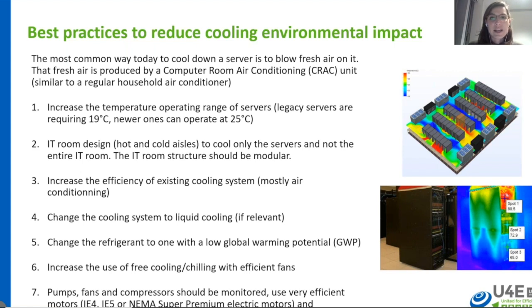For instance, increase the temperature operating range of the server. The second is IT design to cool only the server and not the entire IT room, so the IT room structure should be modular. Data center operations change over time, new servers might be added due to business growth, so it's important the data center can adapt to these changes and save energy on cooling by incorporating modular room designs. We think this is a very important aspect.